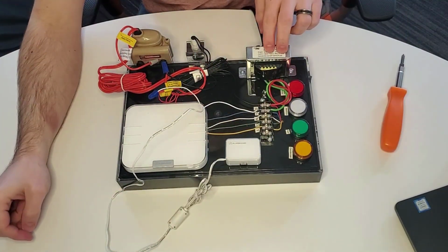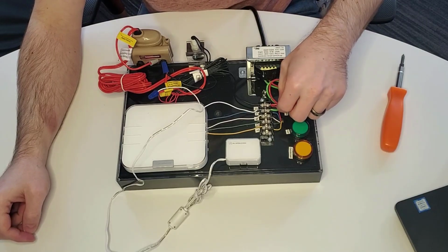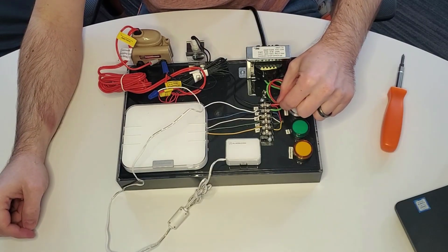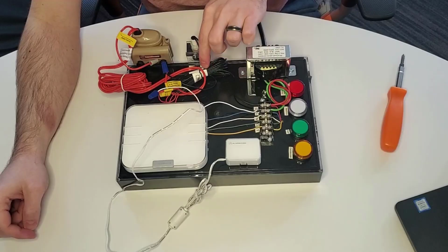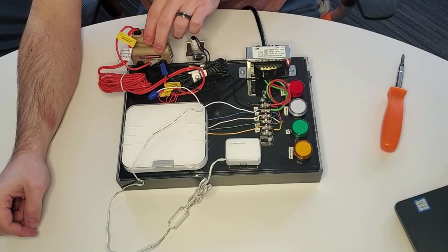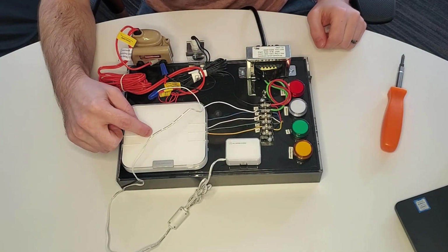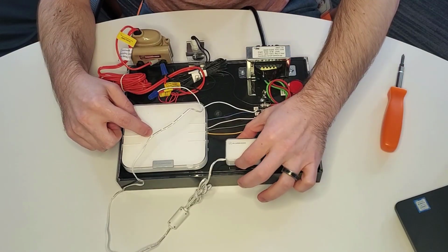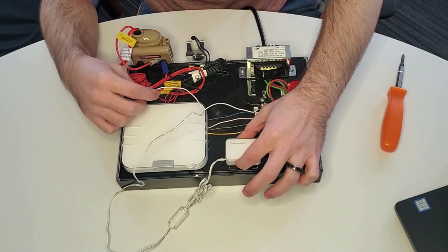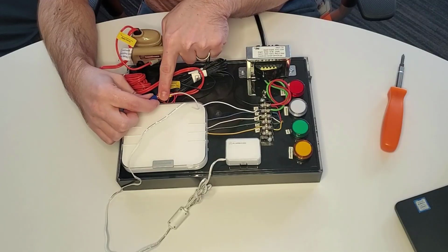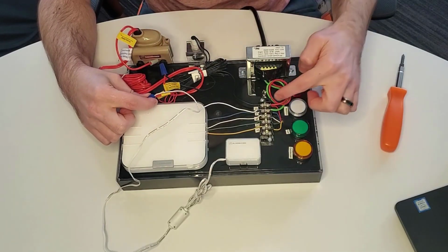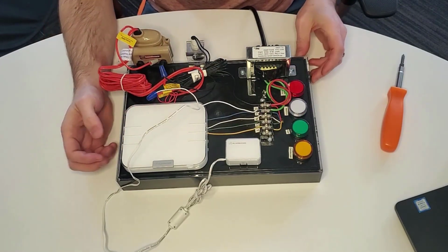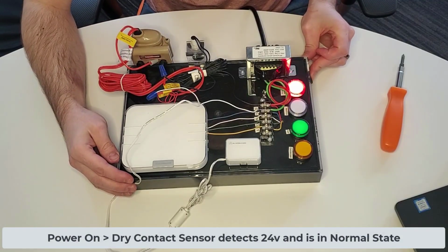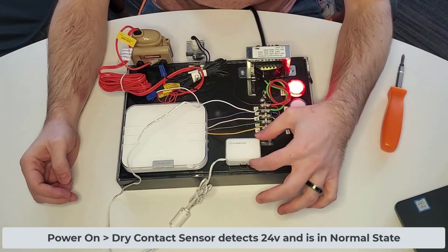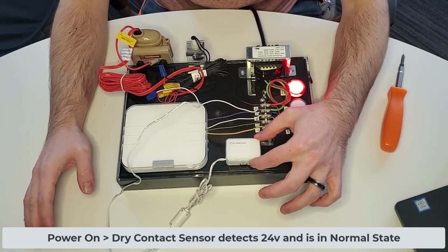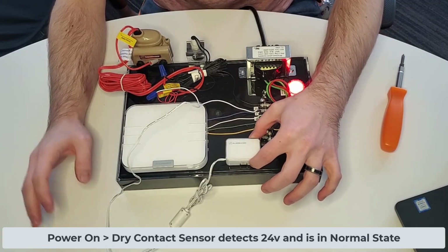So right now, power will leave the transformer, enter our HVAC control board, leave the HVAC control board and go through both of the float switches and then enter the thermostat, and the dry contact sensor will measure the voltage between float switch number 2 and the thermostat and common. So when we power on the equipment, the dry contact sensor sensed the 24 volts and now it is in normal state.